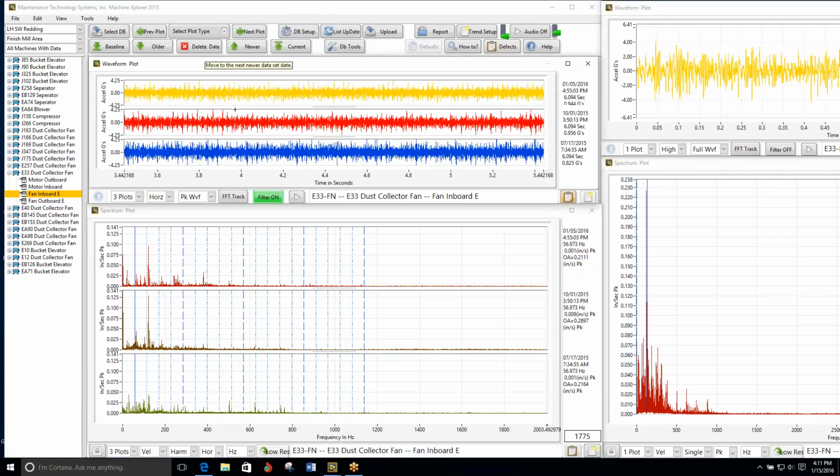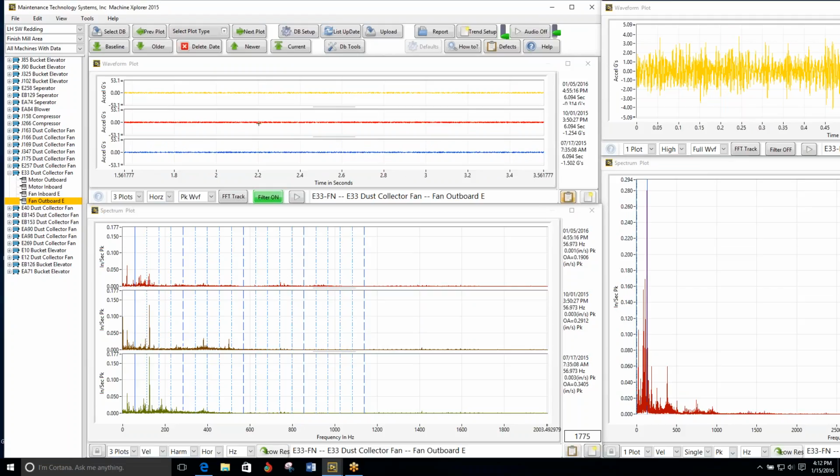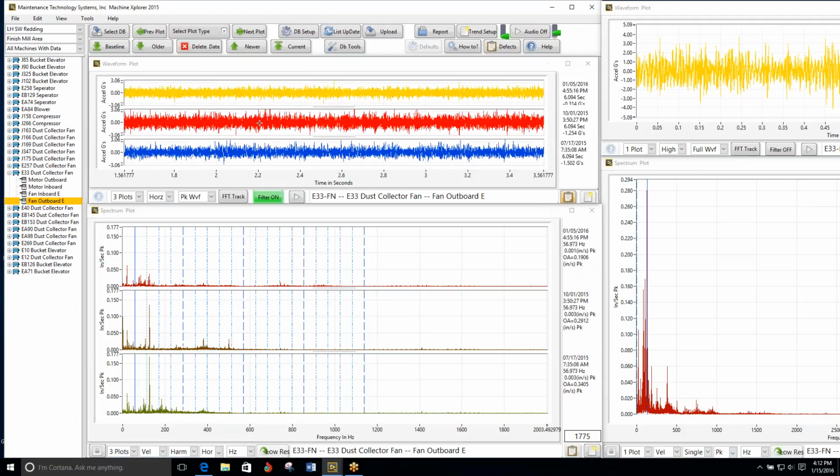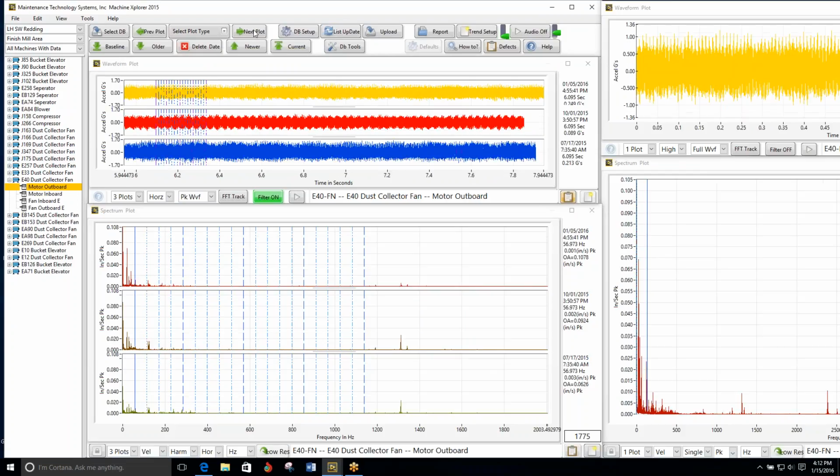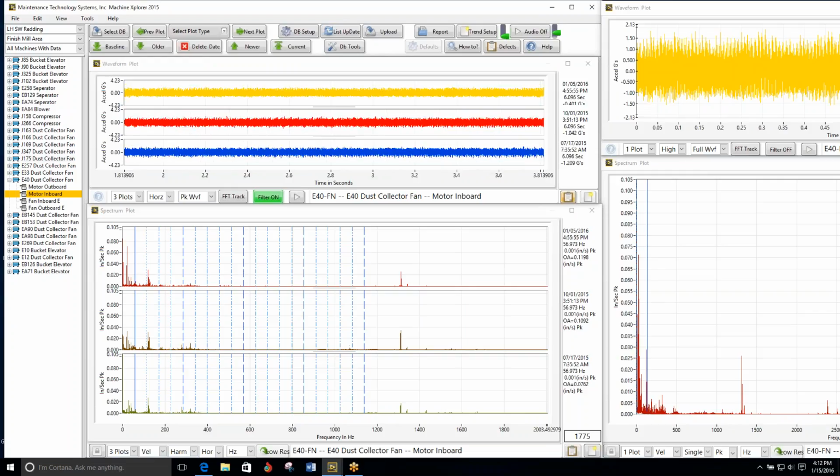That's plus or minus 4 G's. A little bit going on there, but not much. It's been about the same over the last 3 months, or last 6 months. So I'm going to go on. Just running my mouse wheel to pull that up there. 1 G, 2 G's.